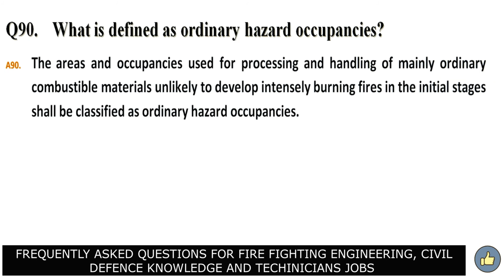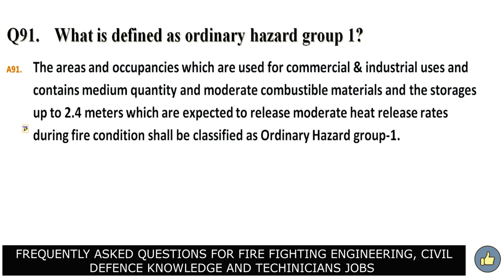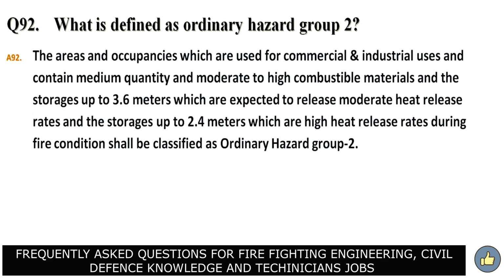What is defined as ordinary hazard occupancies? Answer. The areas and occupancies used for processing and handling of mainly ordinary combustible materials unlikely to develop intensely burning fires in the initial stages shall be classified as ordinary hazard occupancies. What is defined as ordinary hazard group 1? Answer. The areas and occupancies which are used for commercial and industrial uses and contains medium quantity and moderate combustible materials and the storages up to 2.4 meters which are expected to release moderate heat release rates during fire conditions shall be classified as ordinary hazard group 1. What is defined as ordinary hazard group 2?